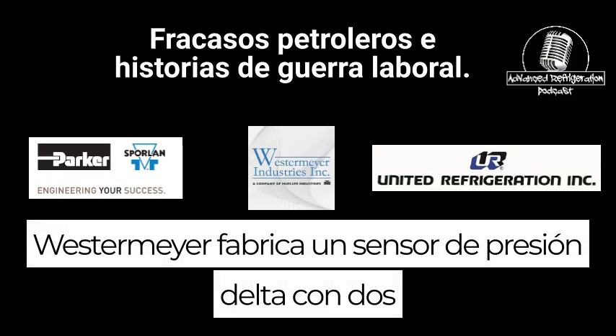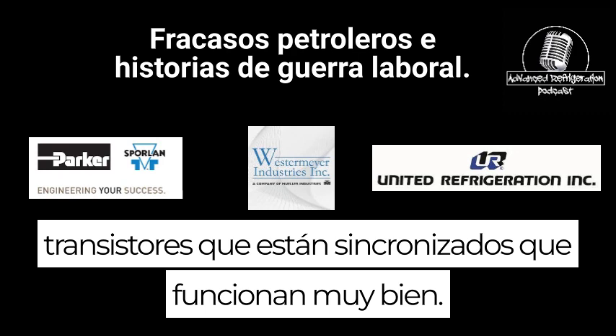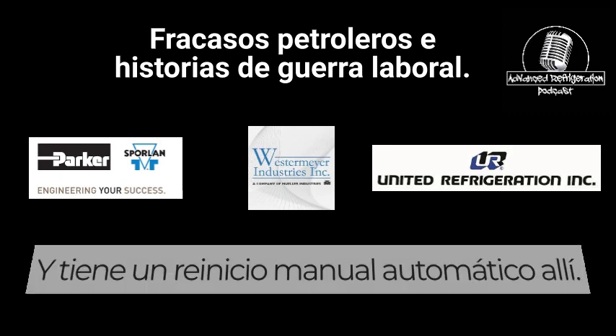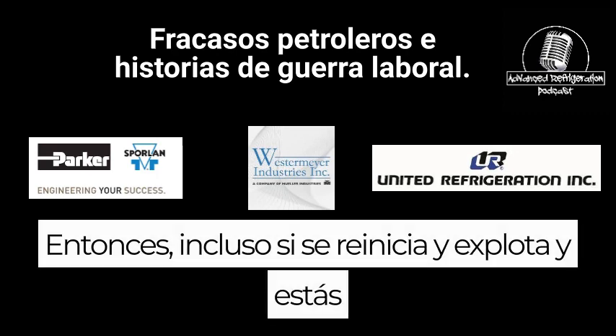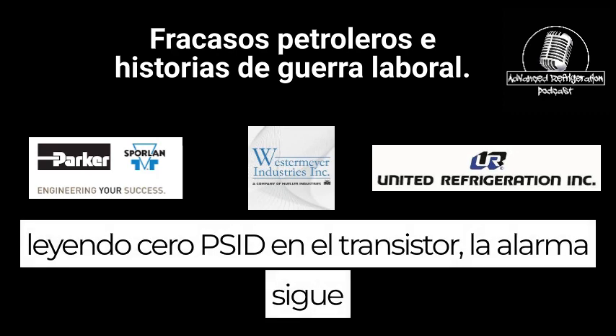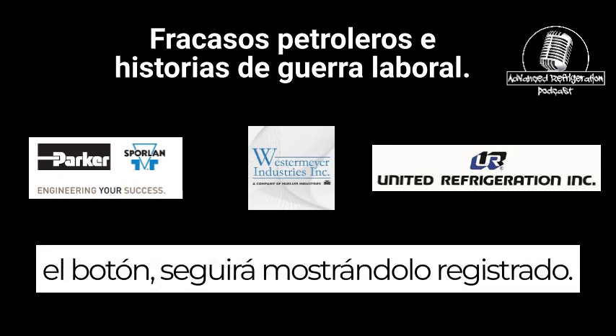Westermeyer makes a delta pressure sensor with 2 transducers that are synchronized. That works really well, and it has an automatic or manual reset on there. So even if it does reset and blow, and you're reading 0 psid on the transducer, the alarm is still on the actual sensor itself. So you reset it, push the button, it'll still show that it registered that.